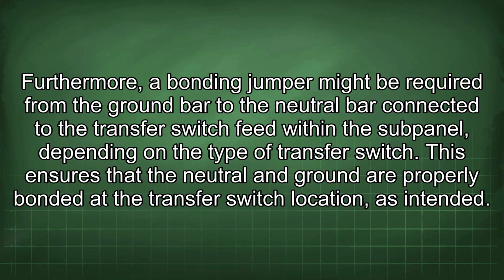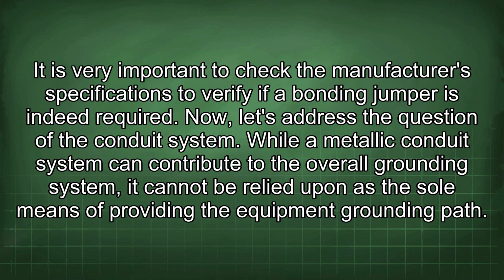Furthermore, a bonding jumper might be required from the ground bar to the neutral bar connected to the transfer switch feed within the subpanel, depending on the type of transfer switch. This ensures that the neutral and ground are properly bonded at the transfer switch location, as intended. It is very important to check the manufacturer's specifications to verify if a bonding jumper is indeed required.